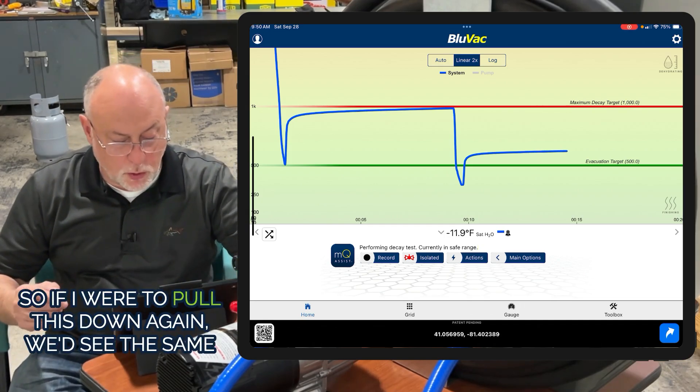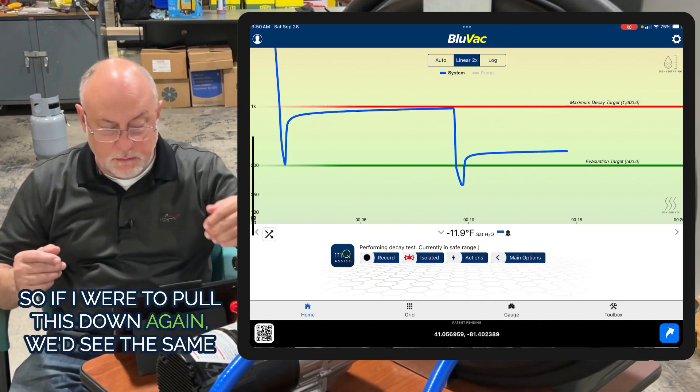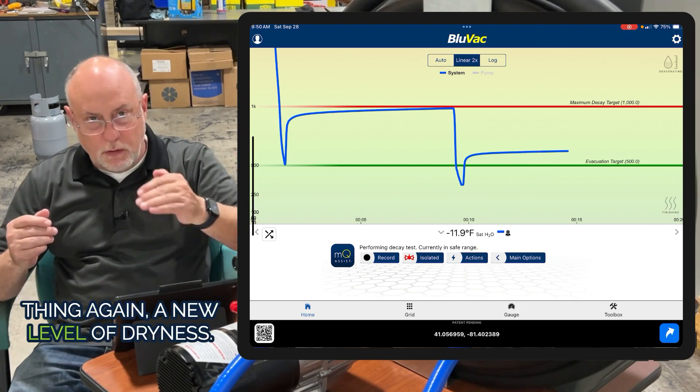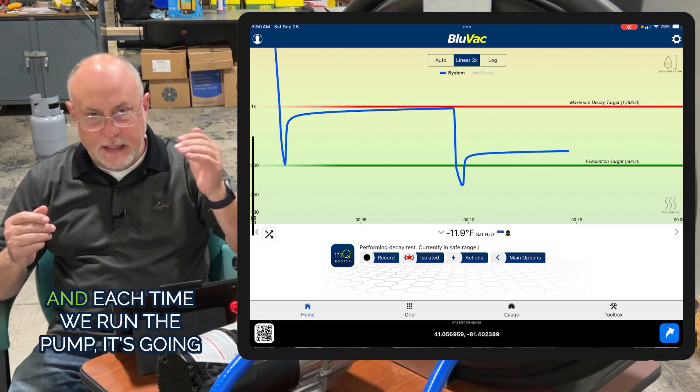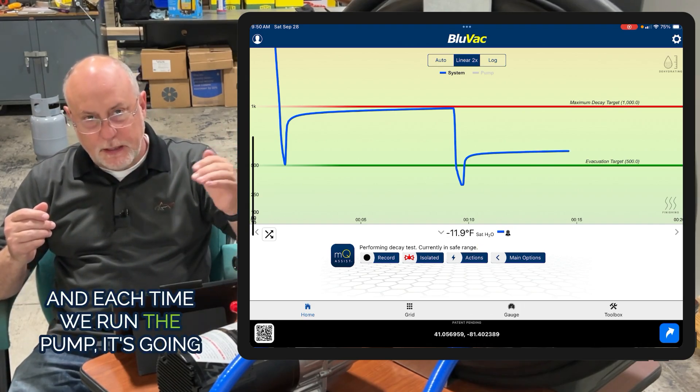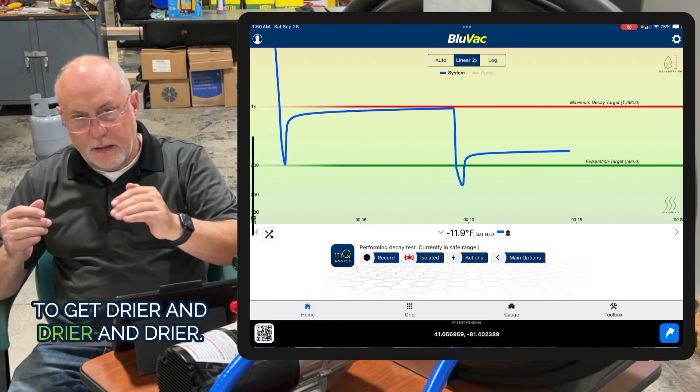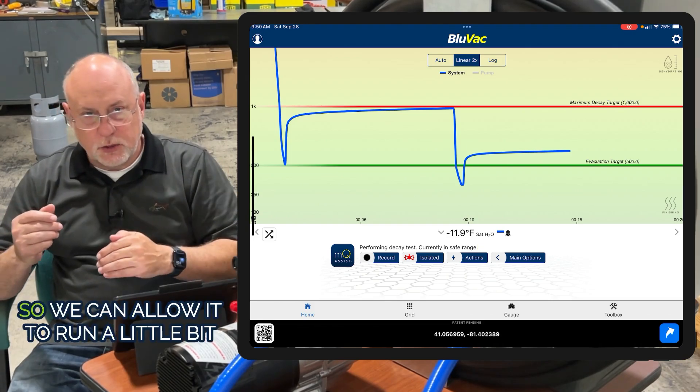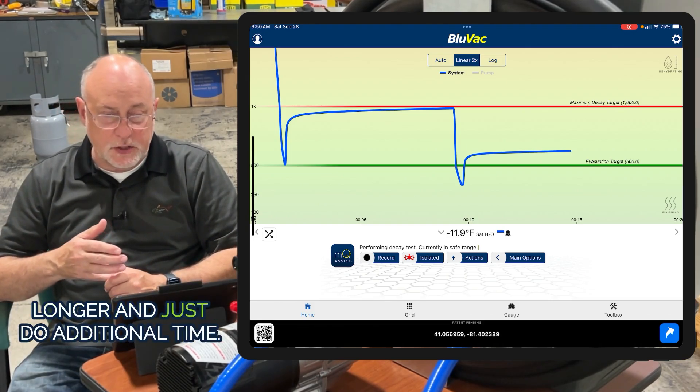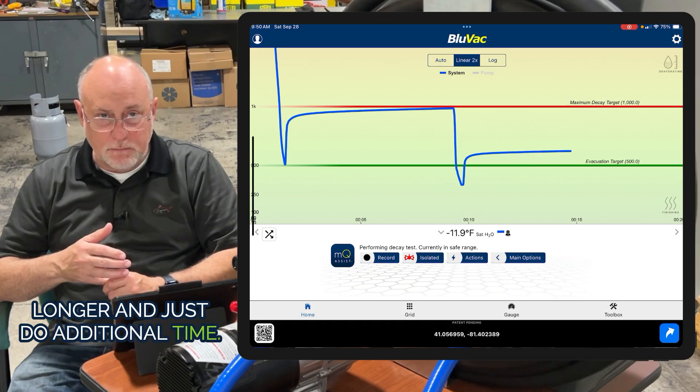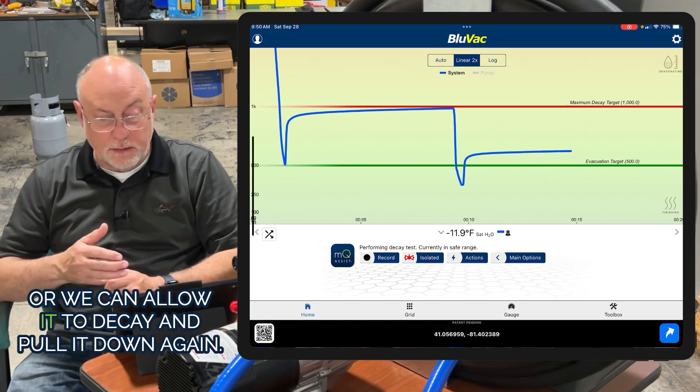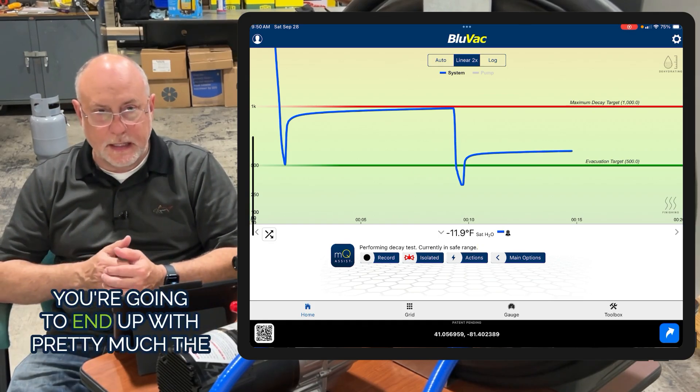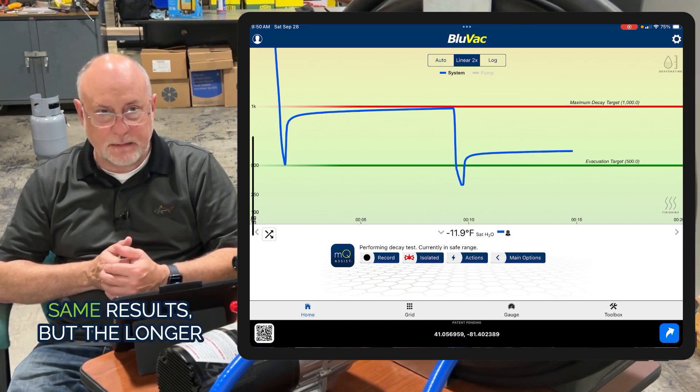If I were to pull this down again, we'd see the same thing - a new level of dryness. Each time we run the pump, it's going to get drier. We can allow it to run longer and do additional time, or we can allow it to decay and pull it down again. You're going to end up with pretty much the same results.